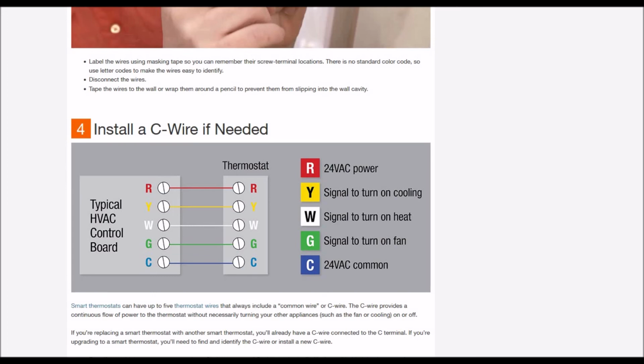So basically, just to summarize really fast, you want to get a multimeter. You want to have it on volts AC, so you can measure AC voltage, and you want to measure from C to R, and be sure you're getting 24 volts AC. If you're not, then you're having a problem either in the wiring or with that transformer. And if you are, and it's still not working, then jumper from R to W, which will bypass the thermostat, and it'll send a signal to the furnace to turn on. If the furnace does turn on, then you know you have a bad thermostat. If the furnace still doesn't turn on, then it's something else inside the furnace itself, and it's not the thermostat or the thermostat wiring. So that's basically it.